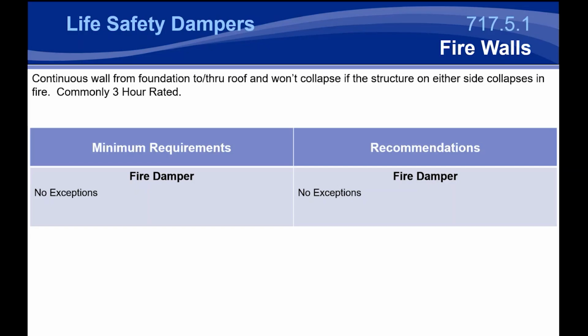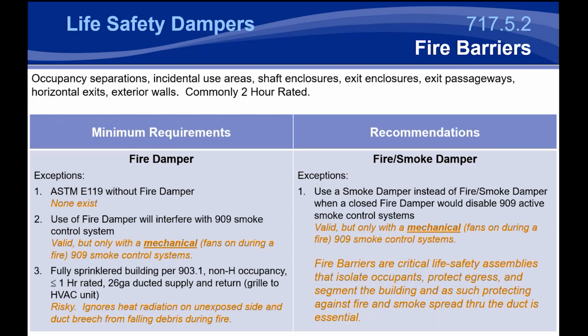Now, these firewalls are different than, say, your exterior wall mounts. We'll talk about exterior walls in a little bit, but these firewalls actually have to be 3-hour rated and structurally independent, so they won't collapse in the event of a fire. So with that, they typically have to have a 3-hour rated damper. You do have to have that protection, but it's very uncommon and a bit different than the exterior wall that I'll talk about. When you're dealing with a fire barrier, you're going to be dealing with barriers that are typically 2-hour rated. And most of the barriers we're going to be talking about from here on out are going to be rated for less than 3 hours.